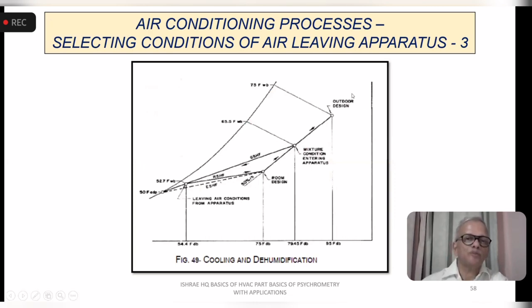This is a repetition of the chart because most of the times you will find the same chart. The moment we talk about psychrometric analysis, you will get this. Only thing is understanding this sensible heat factor, which is telling you the proportion of sensible to latent, and the effect on the ADP and the further system parameters operating, which is like your refrigerant temperature or the chilled water temperature, what could be the limitations? We need to understand and make the analysis.